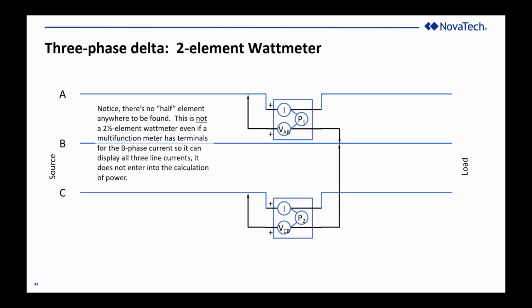This is what a 2-element wattmeter would look like then. You notice by comparison to the 2.5 element meter that I showed you a few slides ago, this doesn't have a half element. This is exactly 2 meters, and you don't have to connect to the B-phase current.